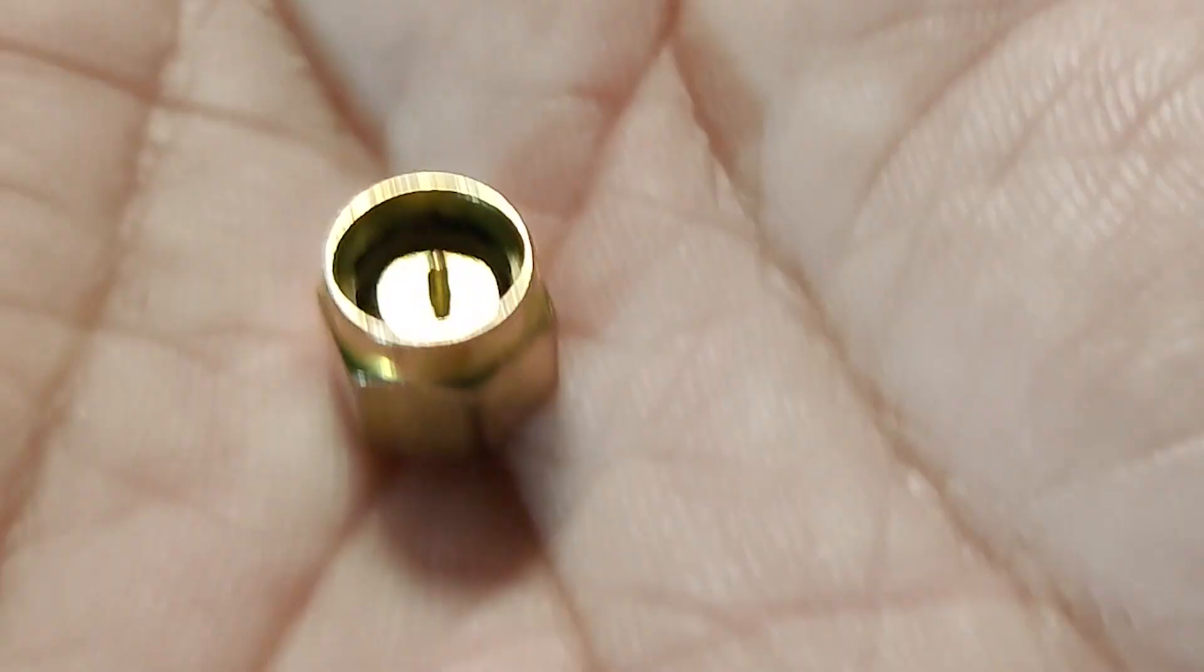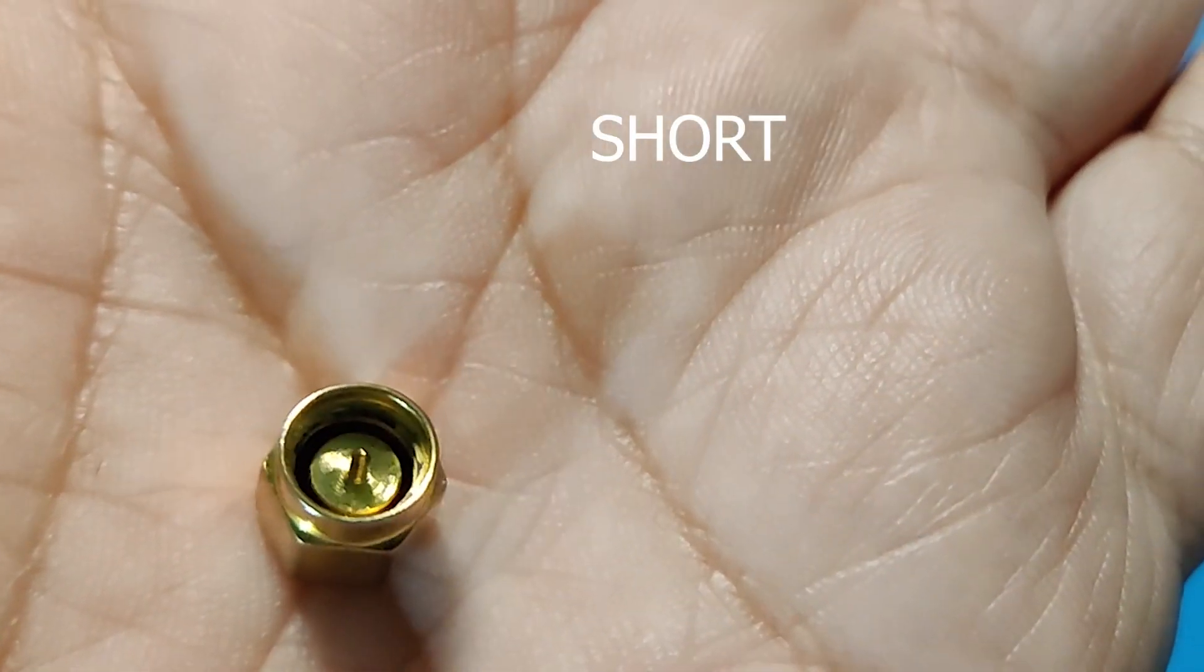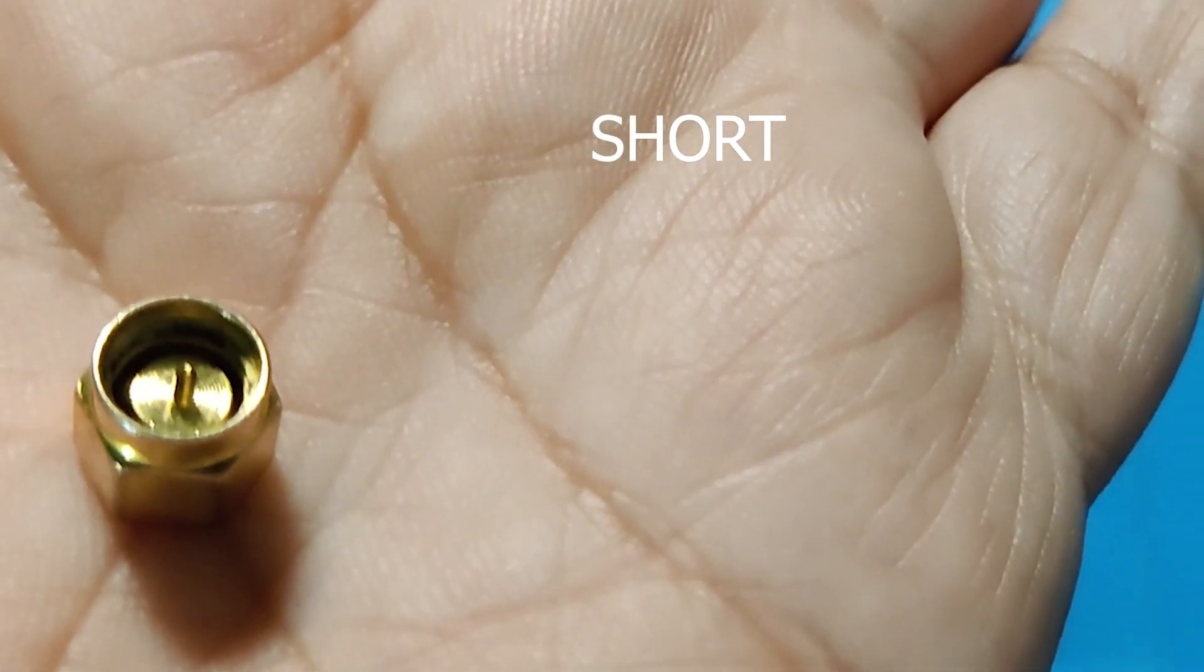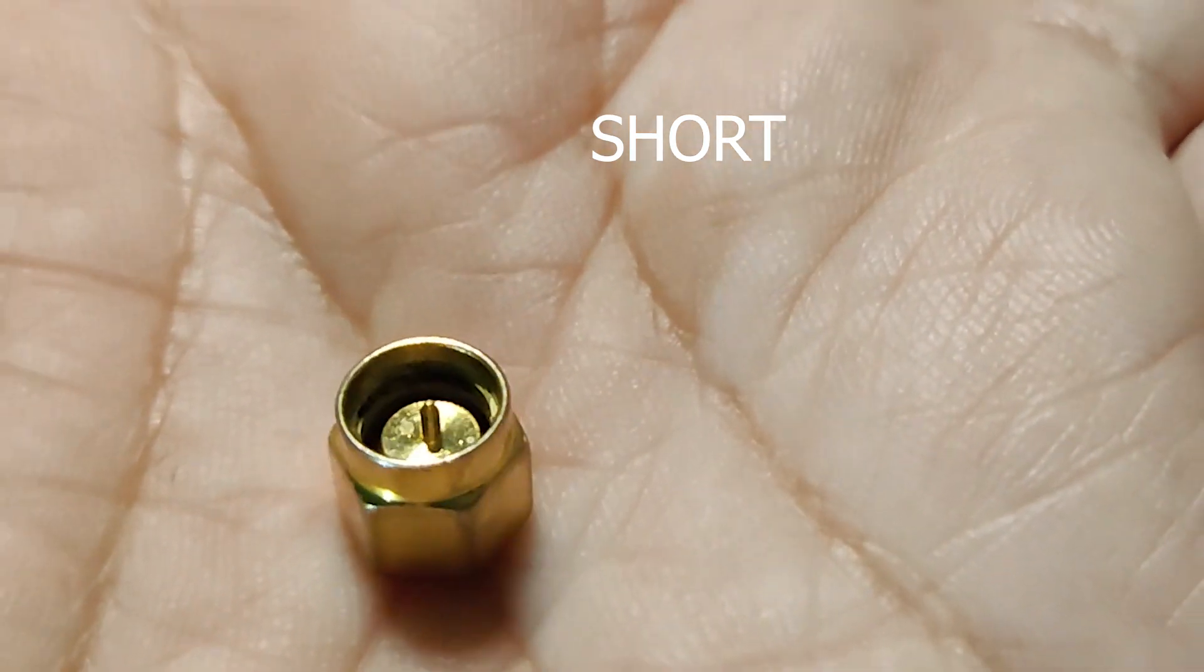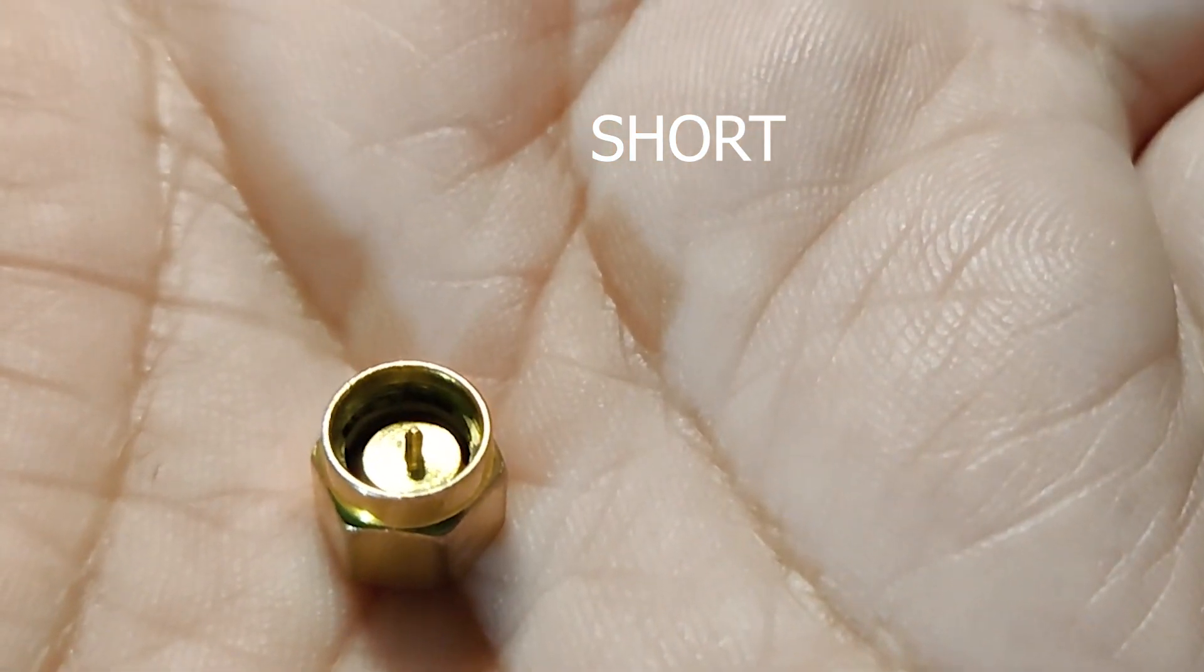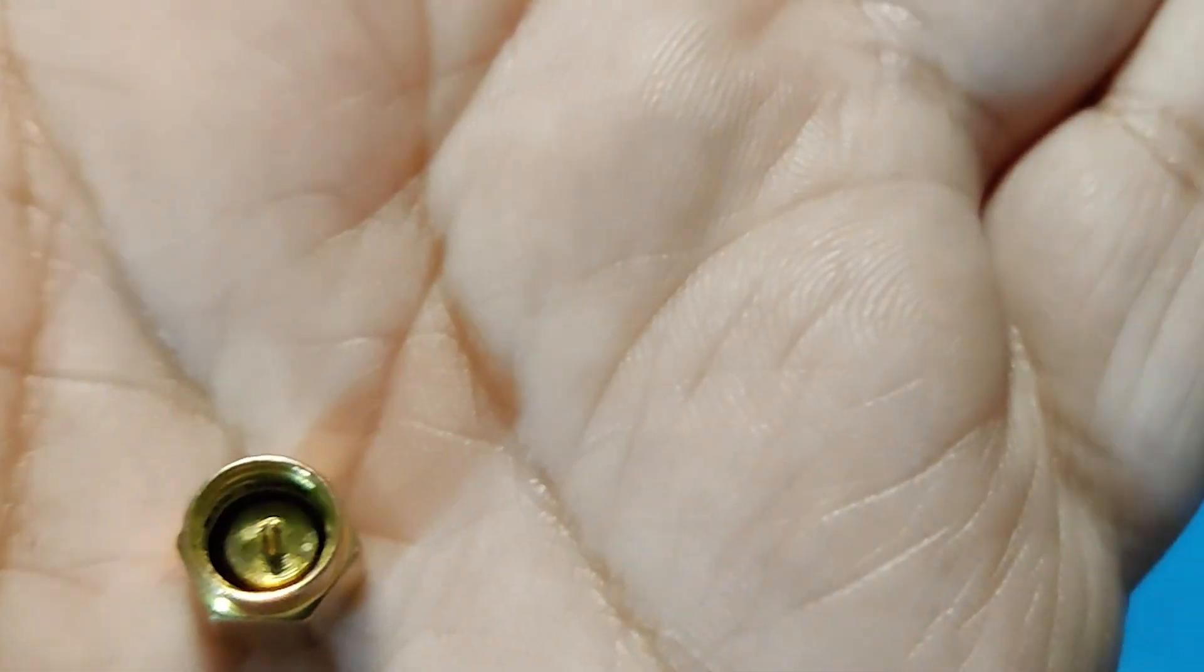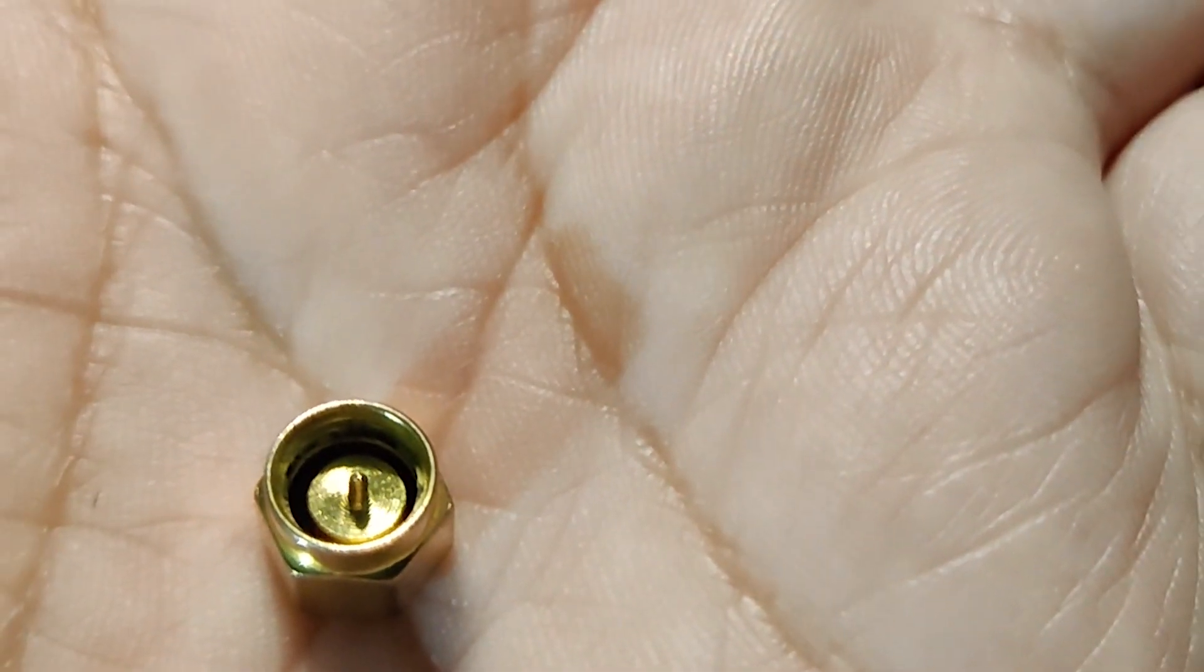This is the short terminator. As you can see, the center pin is connected with the body. There is no insulator between the body and the center pin. So this is short. This can also be verified with a multimeter or ohmmeter.